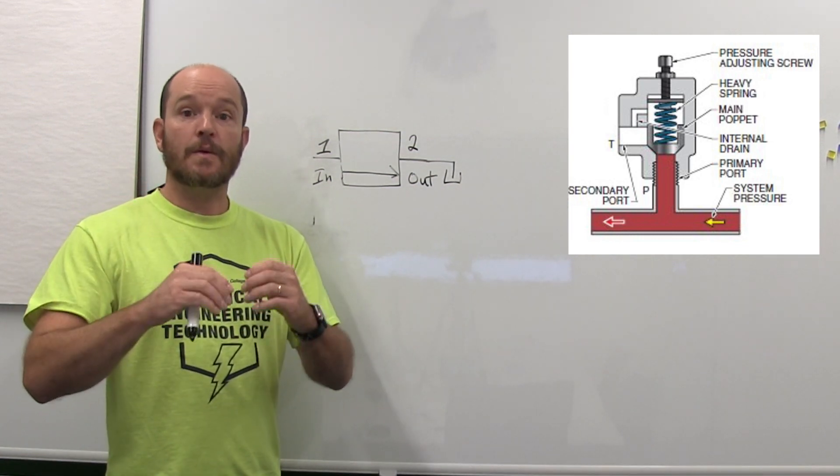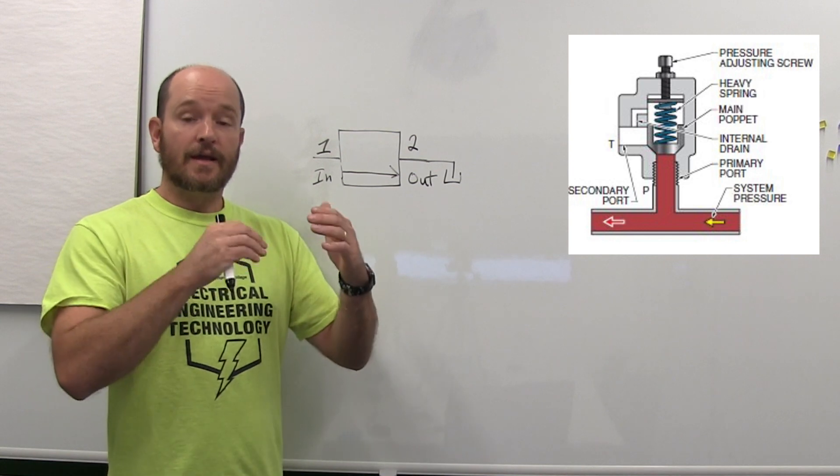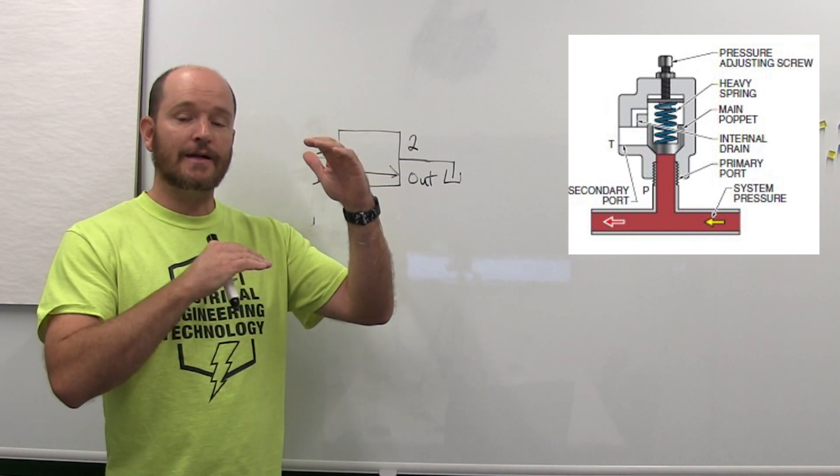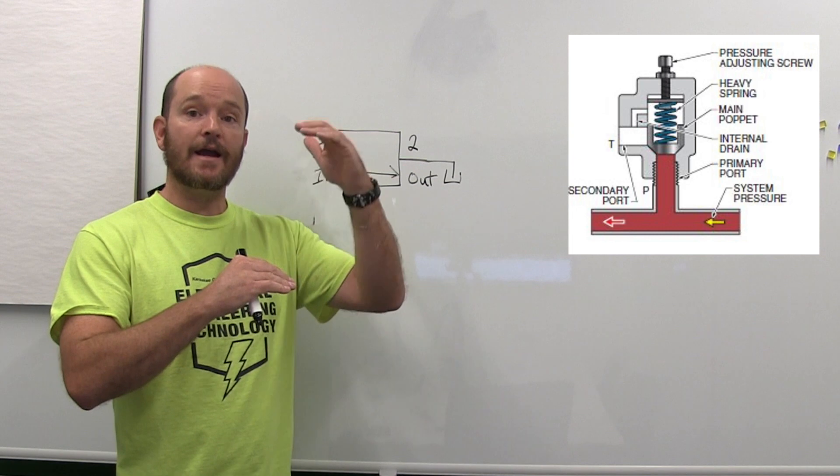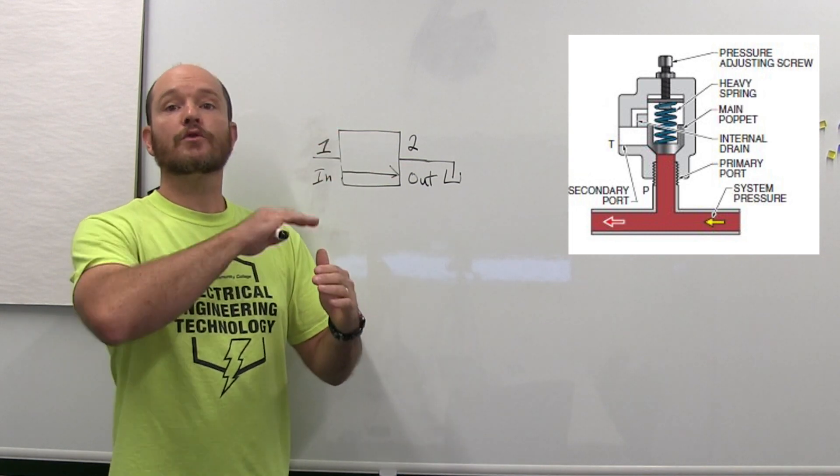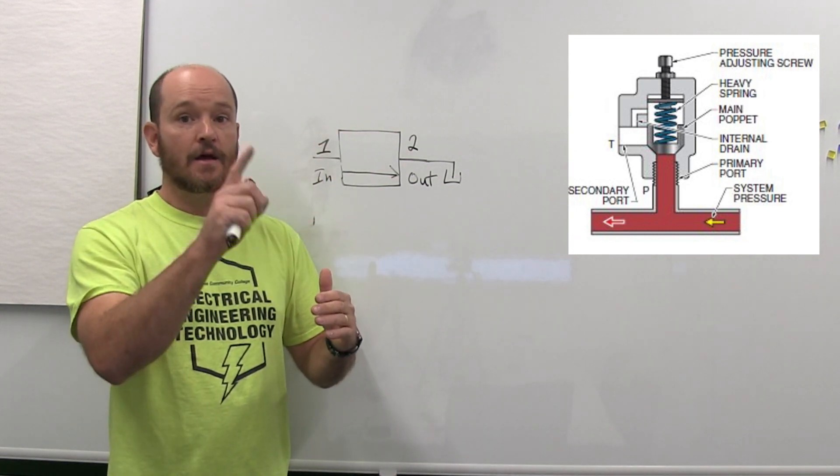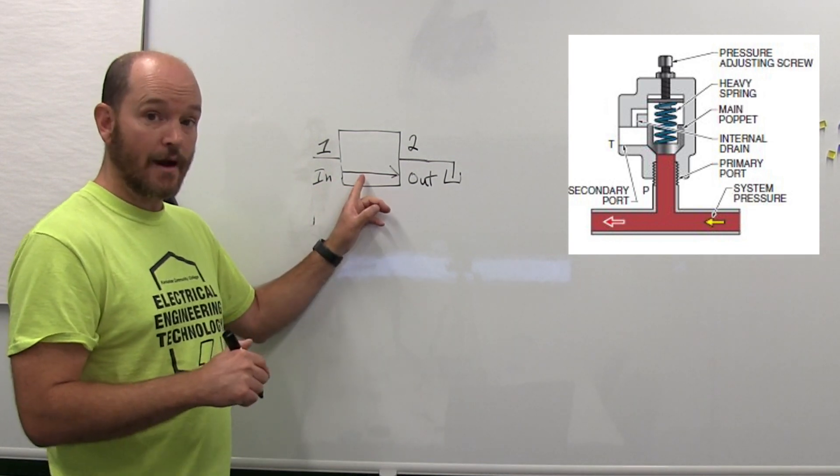The point of the poppet is this is the buffer between your hydraulic pressure and spring pressure. A pressure relief valve compares spring pressure and hydraulic pressure, and if hydraulic pressure is higher than the spring pressure it will send oil back to tank.